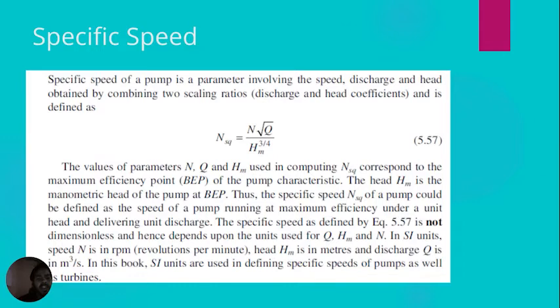Specific speed of a pump is a parameter involving the speed, discharge, and head obtained by combining two scaling ratios — discharge and head coefficient. The formula is Ns equals N·√Q / H^(3/4), where Hm is the manometric head of the pump at maximum efficiency point. The specific speed of a pump could be defined as the speed of a pump running at maximum efficiency under unit head and delivering unit discharge.